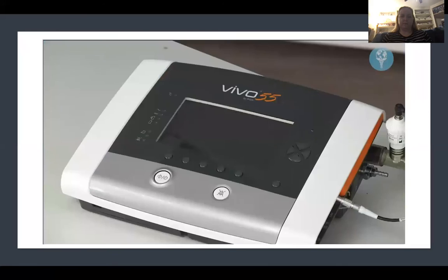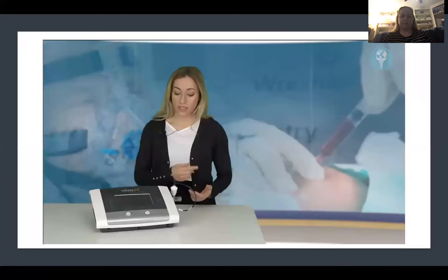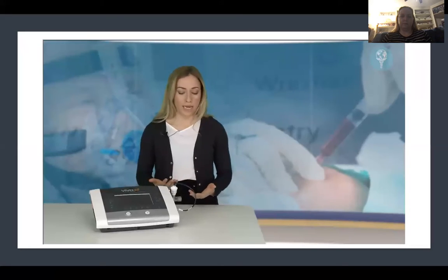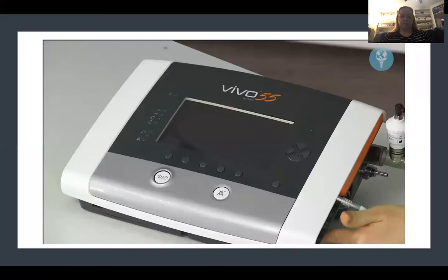So once you've got the FiO2 sensor set up and connected, you'll first need to calibrate the sensor. Your medical physics department may do this for you already. You will need some oxygen entrained through the device in order to perform the calibration. So first you'll need to switch on the ventilator. Just push that on, one push of the button on the side.